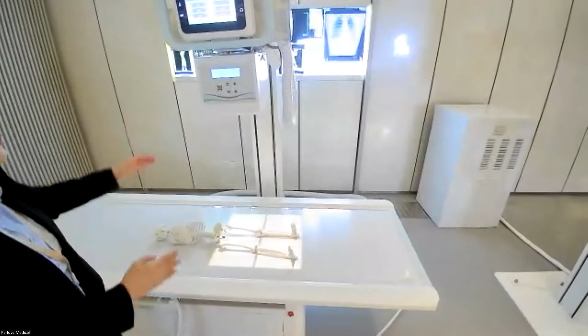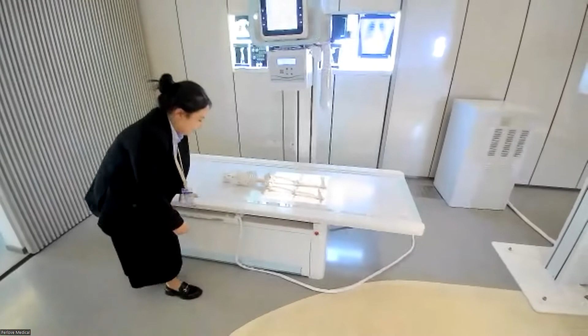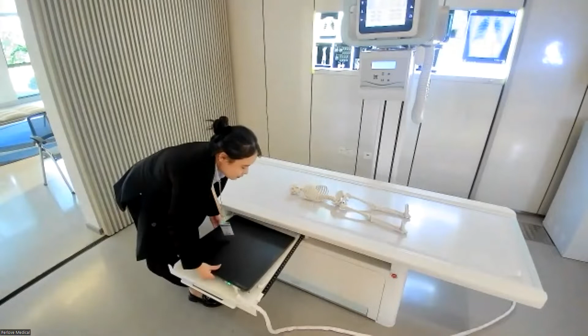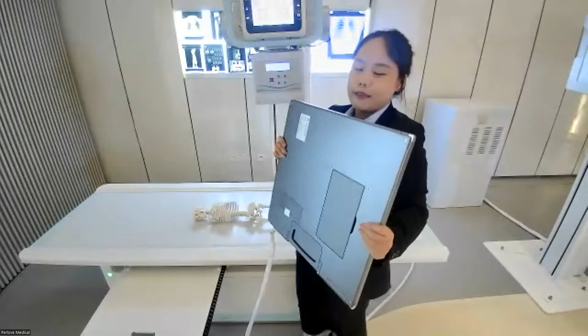So then let's look at our image system. We all know that a lot of digital X-ray systems use a flat panel detector, right? Some use a 14 by 17 inch flat panel detector. Some use 17 by 17. And absolutely, we use the large size, 17 by 17 inch, dynamic flat panel detector. It's very large in size. You can find that it can cover my whole body very easily. So we can reduce the radiation dose, without repeated exposure.